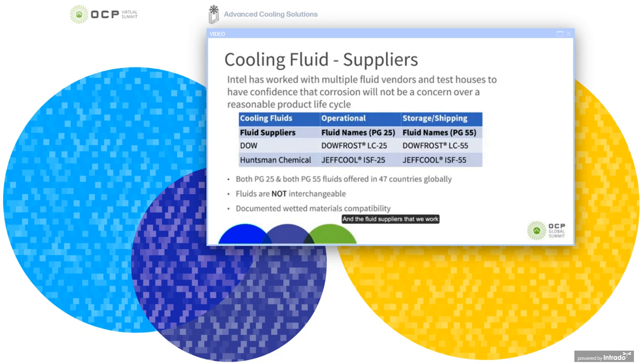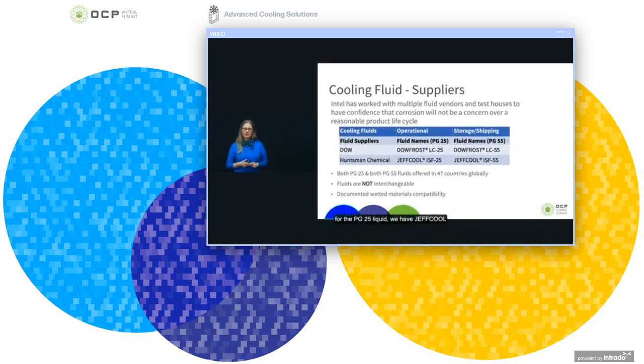And the fluid suppliers that we worked with are two. It's Dow and it's Huntsman Chemicals. And the fluid names, for Dow, we have the Dow Frost LC25 for the 25% propylene glycol level, and for the PG55 for Dow, we have Dow Frost LC55. For Huntsman Chemicals, for the PG25 liquid, we have Jeff Cool ISF 25, and for the 55%, Jeff Cool ISF 55. The reason why we have selected these liquids is that they are globally available in 47 different countries.